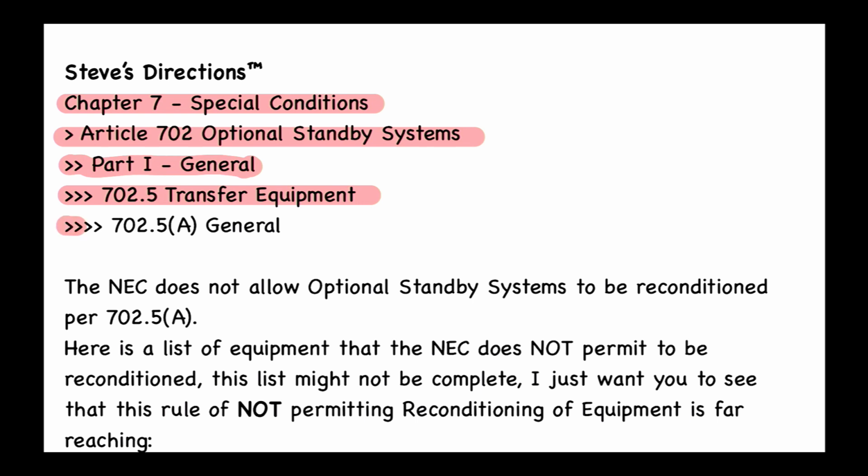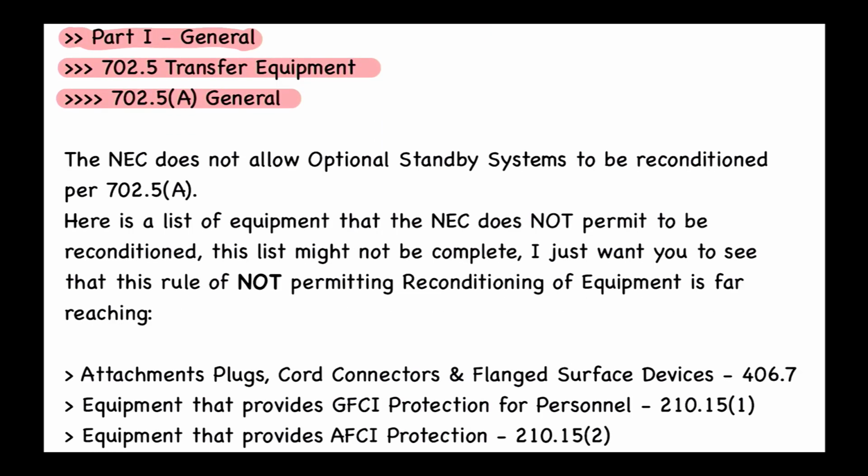Then we find 702.5(A) for general. So again, this is a very, very strict rule that the NEC has. The NEC does not allow optional standby systems to be reconditioned, and this is per 702.5(A). Let me read that to you so that you can really see how strict this rule is in the NEC.